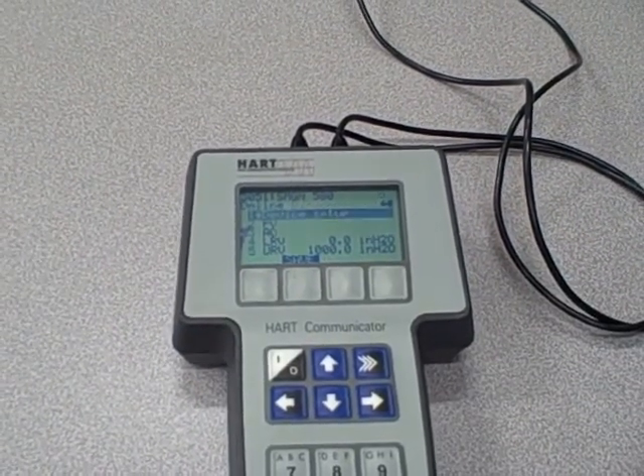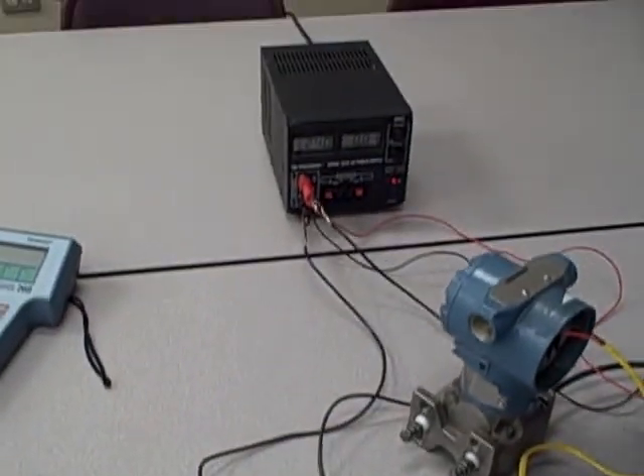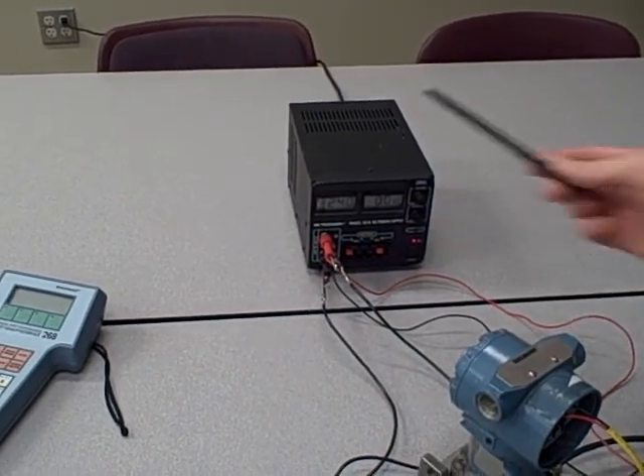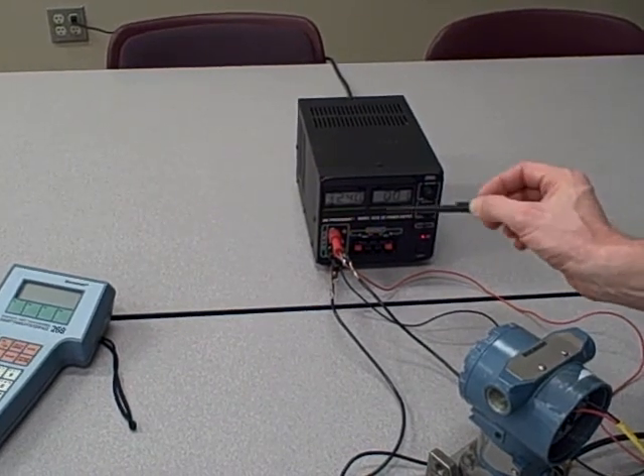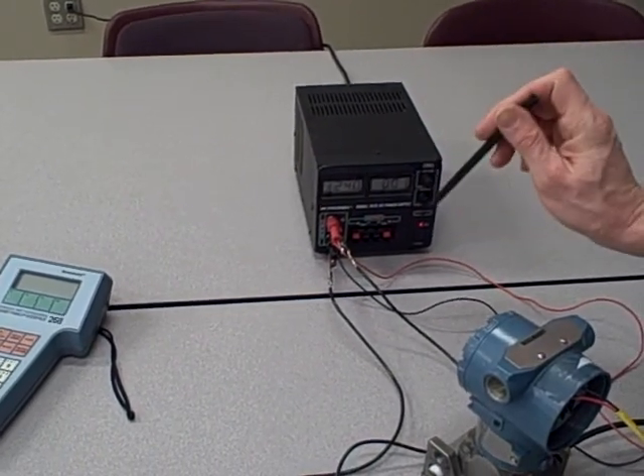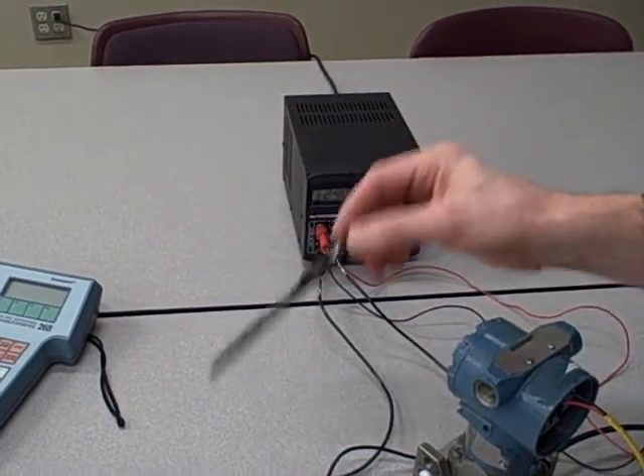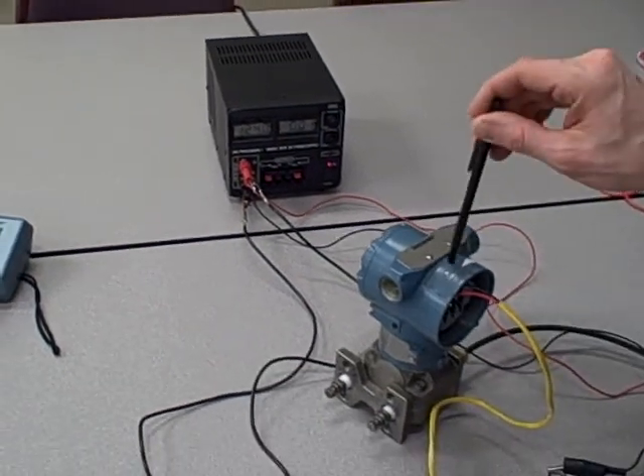The reason for this has to do with the fact this is a DC voltage source. And as a DC voltage source, it has capacitive filtering on the output terminals. That capacitive filtering absolutely kills or squelches any attempt at imposing an AC voltage across those two wires. Therefore, it snubs out the HART signals and does not allow them to exist on the wiring to the transmitter.